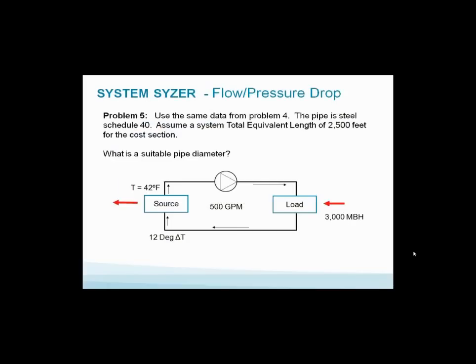Let's take a couple of quick examples on the flow and pressure drop piece. Problem number five: Use the same data from problem four. The pipe is steel schedule 40. Assuming a total equivalent length of pipe of 2,500 feet, we want to understand the operating cost involved. What is a suitable pipe diameter? What size pipe would you pick? Remember the 2,500 feet of pipe would be the equivalent length including the equivalent feet for the T's, elbows, everything. What pipe size for 500 GPM, 42 degree in, 12 degree delta T with a load of 3 million BTUs?